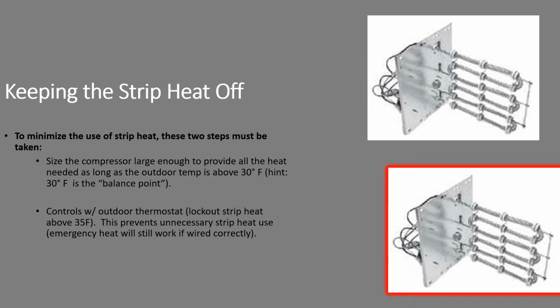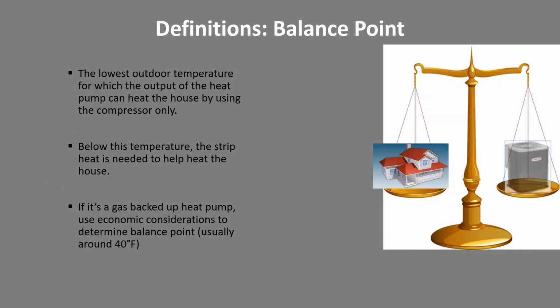Keeping that strip heat off. Well, we have to have controls, and we also have to have the ability to heat the house using the compressor only down to 30 degrees. Balance point. We often hear the term balance point, and it's simply defined as the lowest outdoor temperature for which the output of the heat pump can heat the house by using the compressor only. Below that temperature, the strip heat is going to be needed to heat the house.